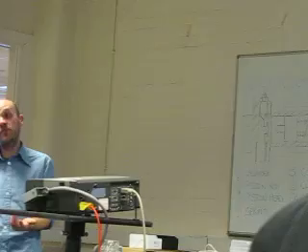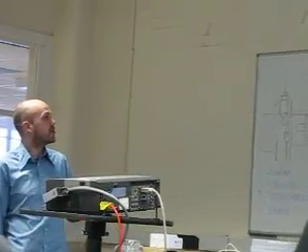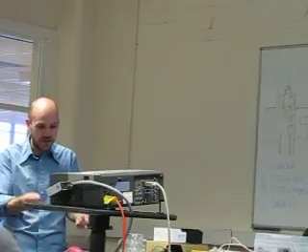So there were definitely issues where, one that I heard about, I went to see, the guy had set it, so everyone had their lights on. The guy had set it so it was okay, he'd then gone off to do something else. And someone had plugged into a rice cooker and turned it on, and it caused instability. The voltage had collapsed, and then everything turned off, and then the micro-hydro system span out of control, and the voltage over-voltaged, and it blew up everything. So it requires a human operator who's there and who's on it, and it's very difficult to do that. You don't really want someone who's employed full-time to look at a valve and move it.